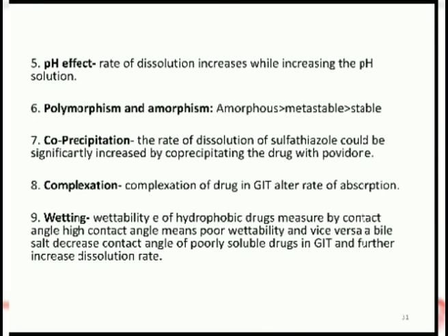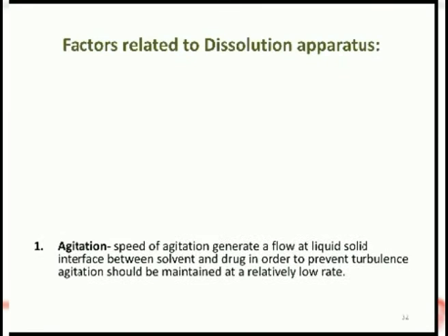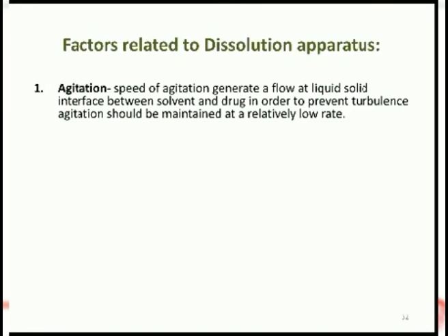During the operation, the tablet is dropped into the dissolution fluid and the fluid is stirred with the paddle positioned vertically near the bottom of the container at the specified speed, 50 to 100 rpm. Samples are withdrawn and analyzed as described above.